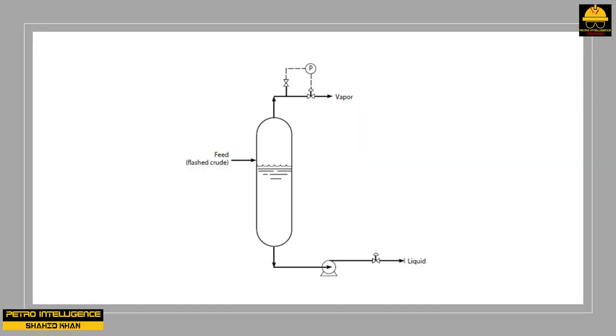This pump was presumed to run fine once running — the available NPSH exceeded the required NPSH. The temporary solution was to suddenly increase the pressure in the drum by partly closing the back pressure control valve. This instantly increases the pressure at the suction of the pump. It is true that raising the pressure in a drum does not increase the steady-state available NPSH, assuming vapor and liquid are at equilibrium, where vapor is at its dew point and liquid is at its bubble point.